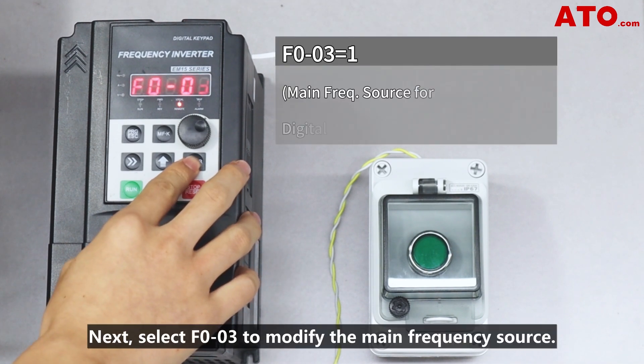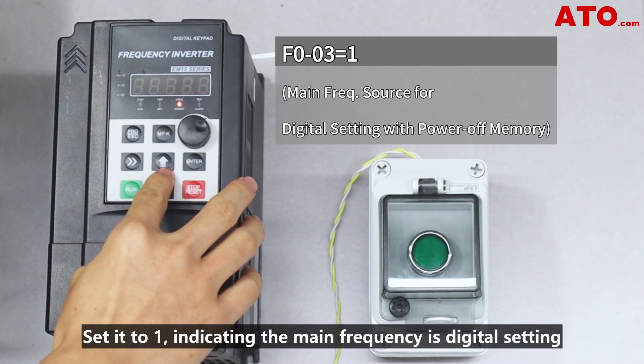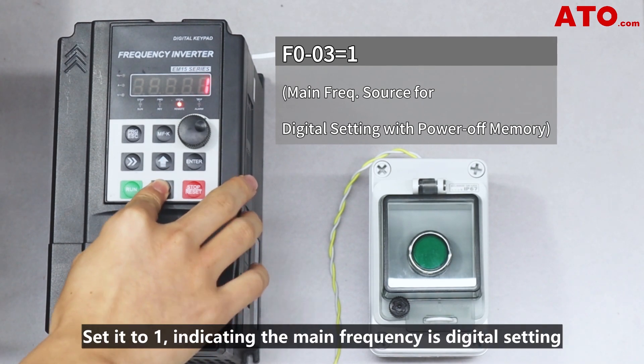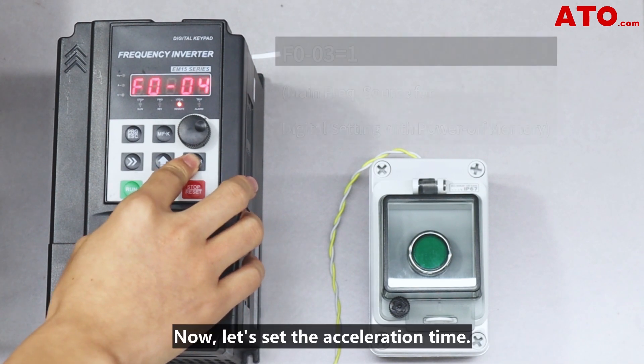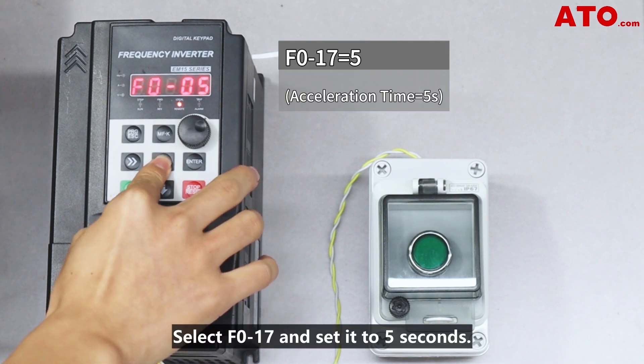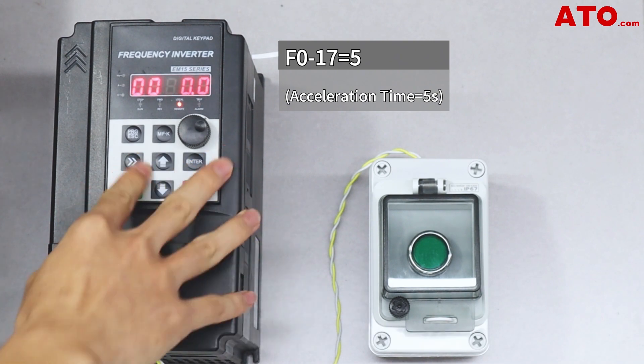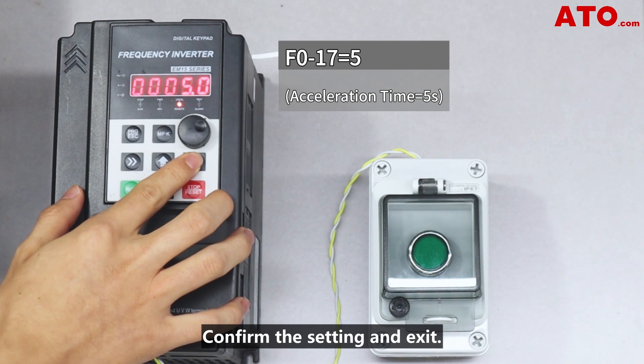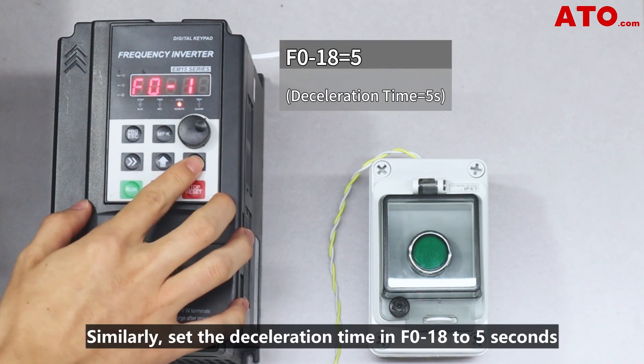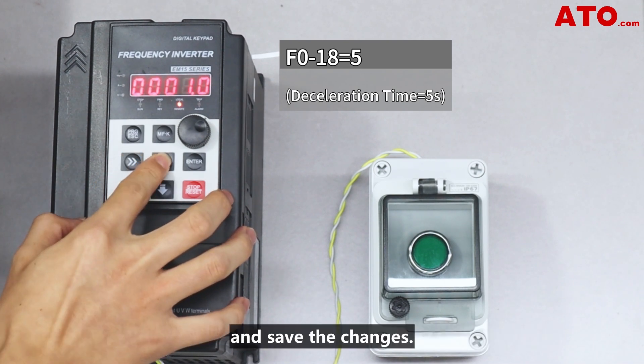Next, select F0-03 to modify the main frequency source. Set it to 1, indicating the main frequency is digital setting and retains its value during power off. Now let's set the acceleration time. Select F0-17 and set it to 5 seconds. Confirm the setting and exit. Similarly, set the deceleration time in F0-18 to 5 seconds and save the changes.